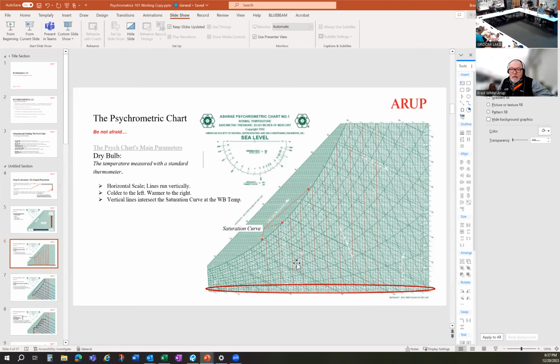So I'm trying to understand the relationship between the three items. I'd have to do a unit conversion from kPa to inches of mercury. But the vapor pressure is the motive force that drives moisture one way or another, irrespective of airflow. So if I've got a surface of a wall, or the boundary of a humidor, or a dividing point between two areas of measurably different humidity ratios, the vapor pressure difference measured in those finite units is the motive force.